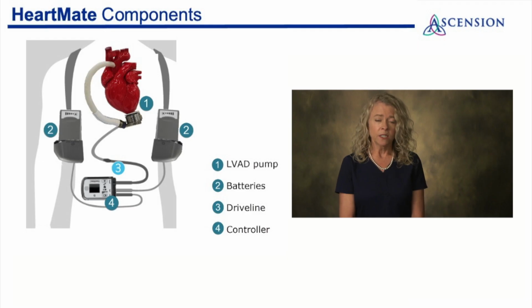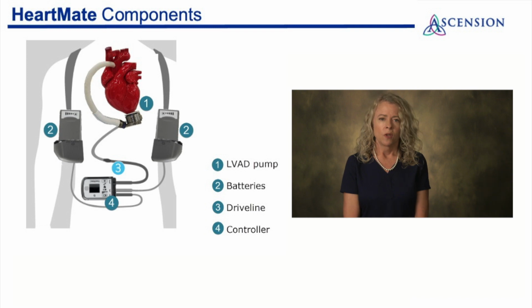The driveline connects the VAD pump to the controller. For HeartMate 2, the driveline is a solid cable, and if there's any damage, it may or may not be repaired. In other words, depending on how bad the damage is, the VAD, meaning the whole entire pump it's connected to, may need to be replaced. Some of these patients have had their VADs for many years. VAD patients get really comfortable with their device and they forget it's there, so they get stuck in doorknobs, in car doors, or chewed on by pets.